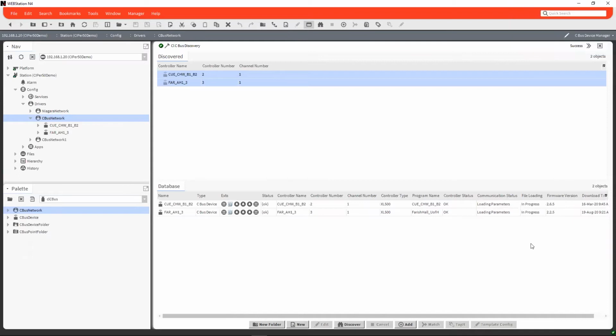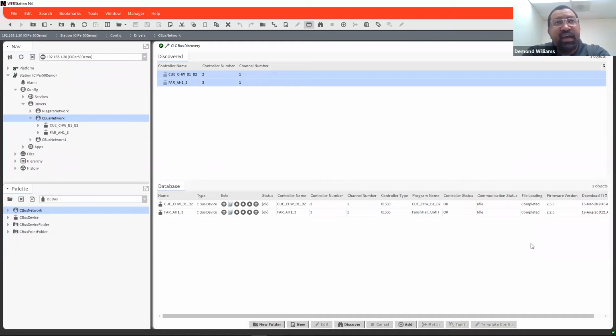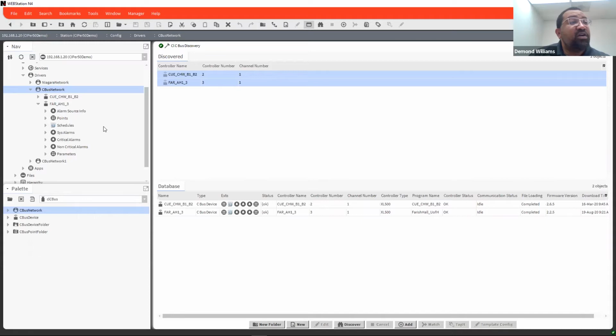Hey, Demond. Yes. Back on the zone controllers, when you have VAVs under that, when you do a discover, does it come in with the descriptions of VAV1, VAV2, space temps, discharge temps? So yes, it will keep whatever name that Honeywell or however they programmed it in CARE, it will keep those exact same names. So you won't have to try to figure out what this point is or anything like that. So if they actually named it room temp, when we discover it, it actually will say room temp, setpoint, or anything like that. And then I would imagine we'd probably want to create a points folder with VAV1 so that we could copy those points, put them in there to keep graphics all relativized. Yes, so that's the only thing.